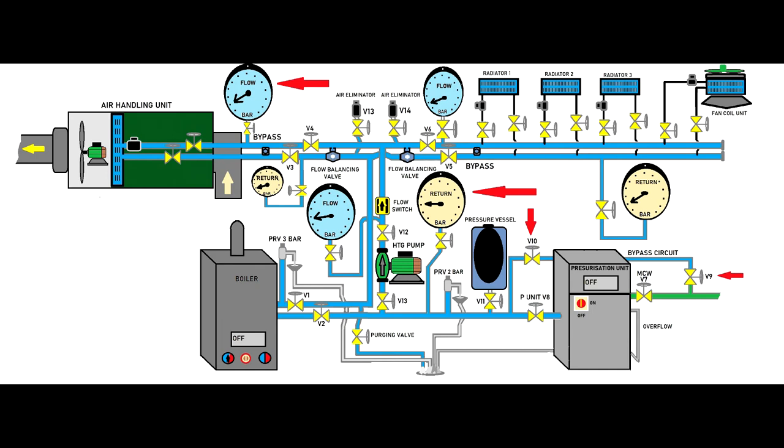And that will be the reference points for you when you fit the manometer to create reference points for further maintenance when you install HVAC equipment. If you look at this gadget, the gauges that sit on the ground show slightly more pressure than the one which sits on the top. I put them this in purpose to give you a kind of example what would you expect when the pumps are not running. Once I decided that the system is filled up and it is full with water, I will turn off the bypass valves and I will pass the duty to the pressurization unit.